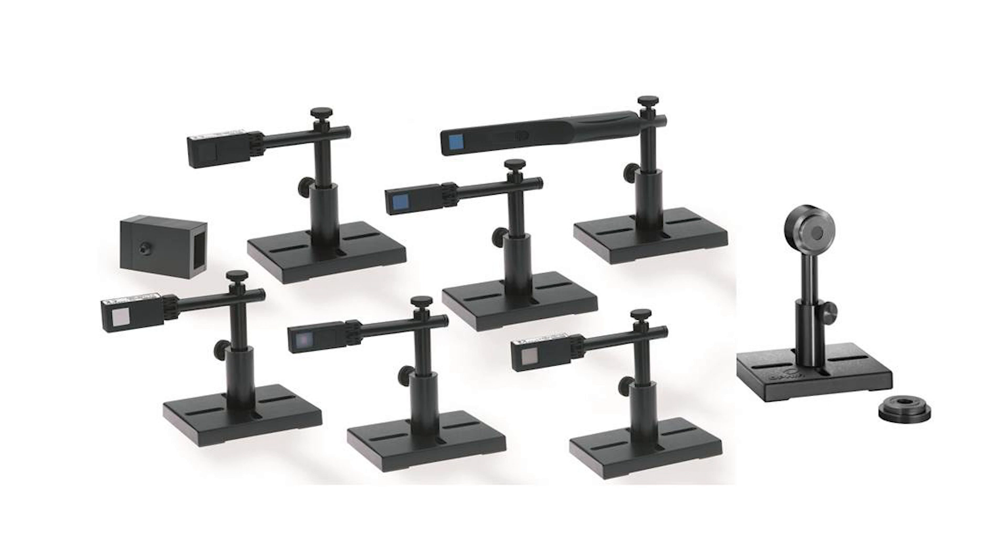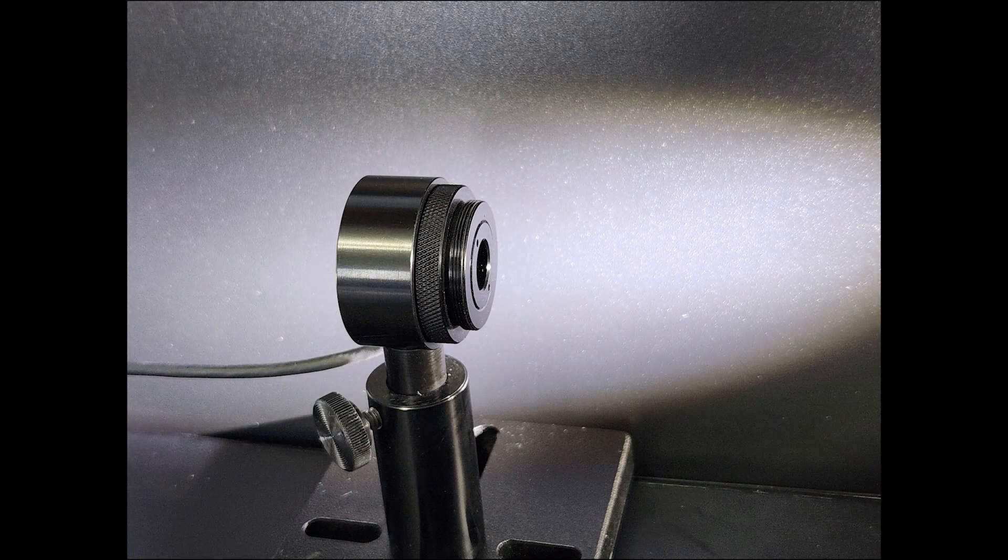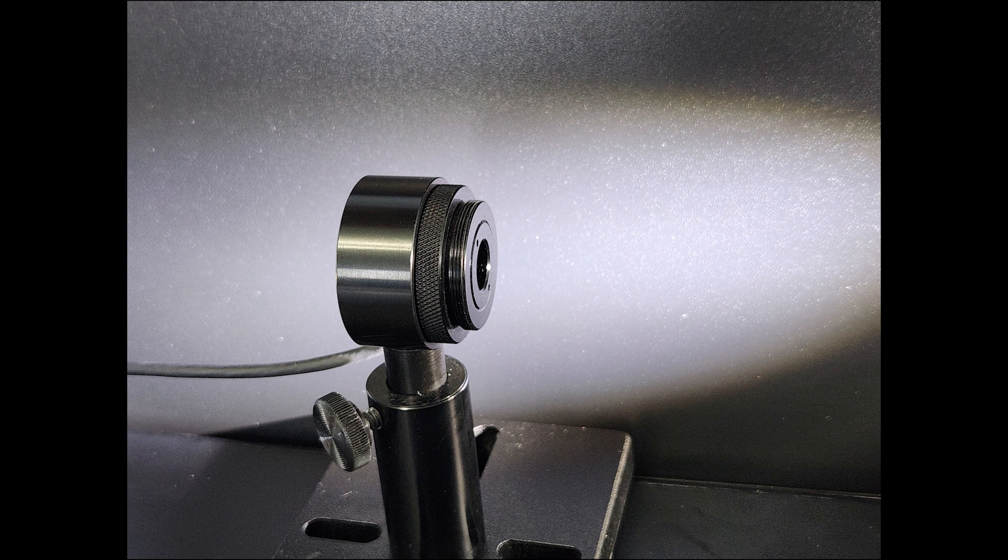You could use a photodiode-based sensor. That's usually what you'd use for such low powers. But the beam is widely diverging, and a lot of it might just miss the sensor's aperture unless you bring it really close. Also, photodiode sensors usually have a strong angle dependence.